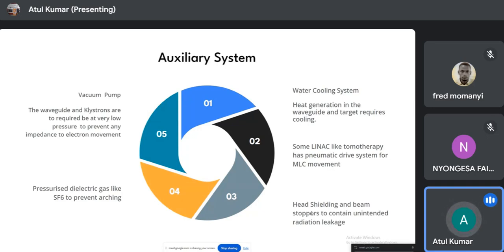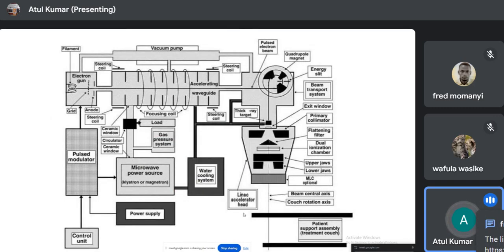This is a typical design of a LINAC. If you look closely, you have your pulse modulator, which gives pulses to the RF source, the microwave, magnetron or klystron, whatever you have. Then this RF wave is fed into the RF system. You have an electron gun, and the beam is bent through here. Then you have your primary collimation, secondary collimation, your flattening filter, ion chambers, MLCs, couch, and several other things. That's all. Thank you very much.